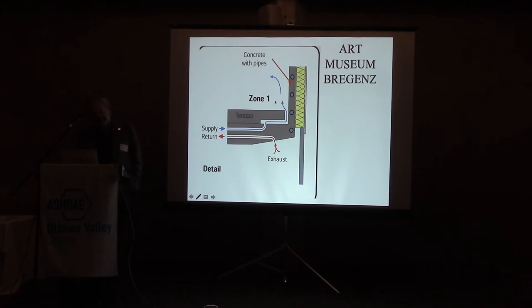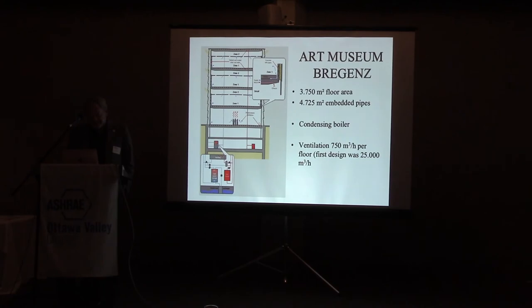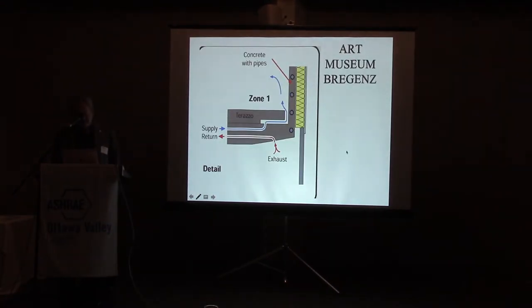But by going for this hydronic removal of heat, both for heating and cooling, you could avoid a lot of air. Instead of having 25,000 cubic meters per hour for each story, we only needed 750 cubic meters per hour by doing most of the heating and cooling with a hydronic system.